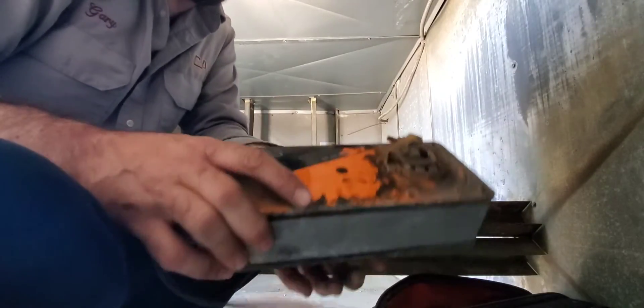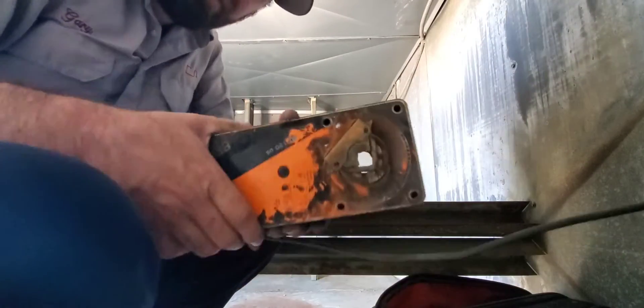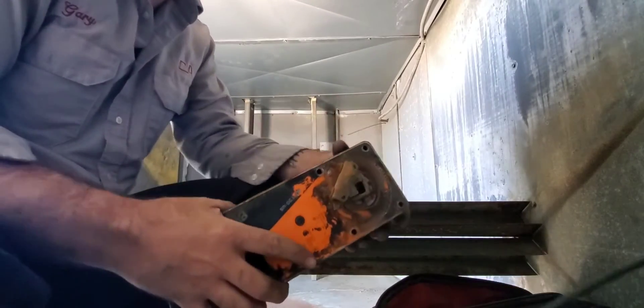All right, so we're inside of Makeup Air. It's direct fired. The fresh air dampers are behind the camera. You can't see them. I'm changing out this Belimo actuator because it has failed.